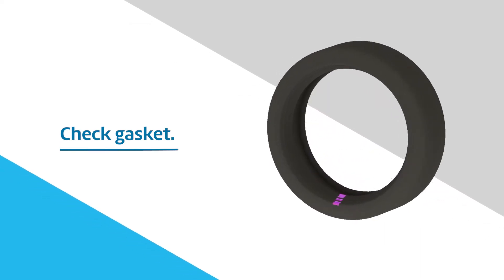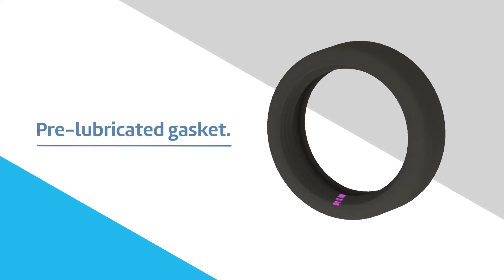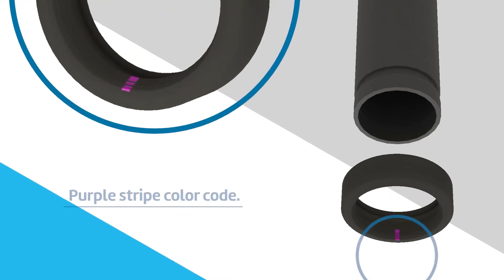The FP7400 Rigid Light Coupling has a pre-lubricated Grade E EPDM Type A gasket intended for use in fire protection systems installed in accordance with NFPA 13 standard sprinkler systems. The gasket is identified by a purple stripe color code.